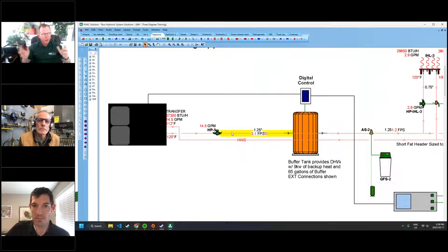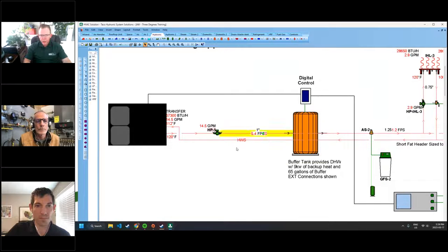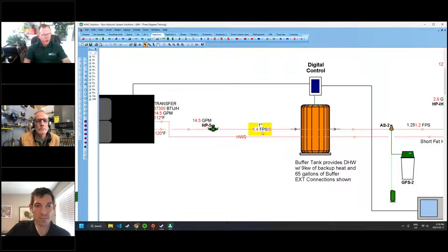We don't want to be having really high flow velocities going through it. And if I was actually going to change this piping and turn it into some 1-inch piping, we're going to find that very quickly the flow velocity and head loss is going to increase. At this point, I'm creeping up to almost 6 feet per second. And goodness forgive that if we put 3/4 inch on this, which the math says for a boiler we could do, you can imagine what would happen here with flow velocity and everything else that comes into play.